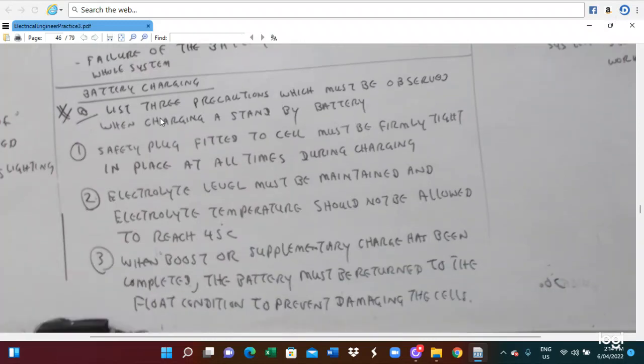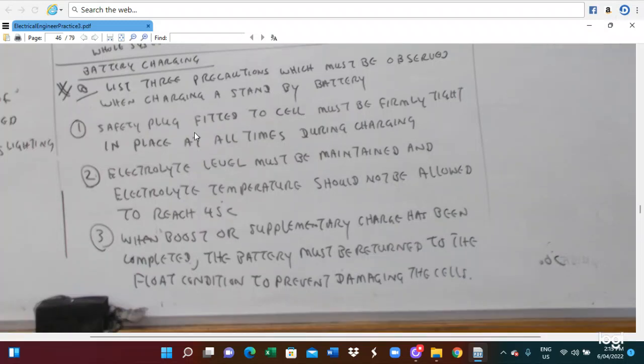And the next one is battery charging. These are three precautions which must be observed when charging a standby battery. The safety plug fitted to the cell must be firmly tight in place at all times during charging. Electrolyte level must be maintained, and the electrolyte temperature should not be allowed to reach 45 degrees centigrade. When the boost or supplementary charge has been completed, the battery must be returned to the float condition to prevent damage to the cells.